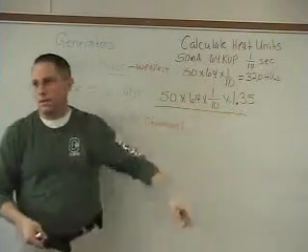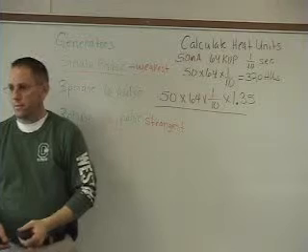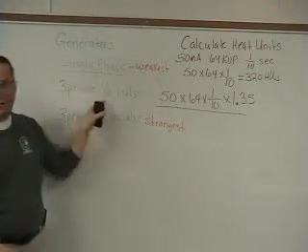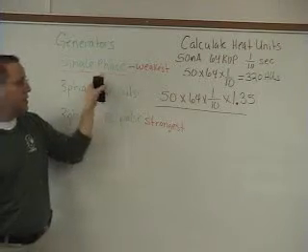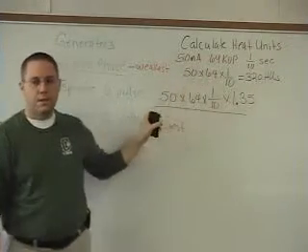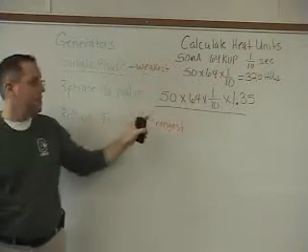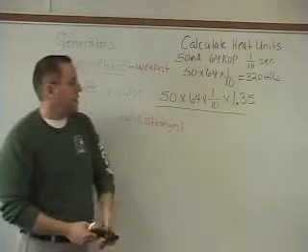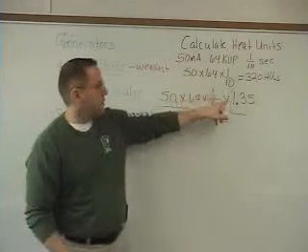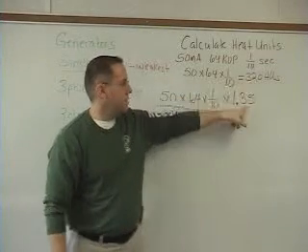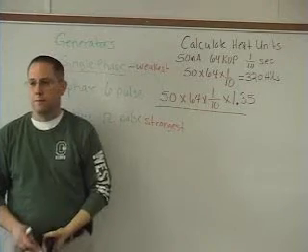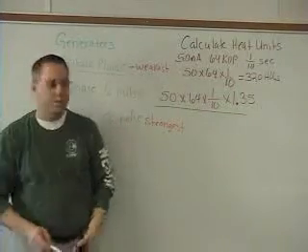That number always stays the same, 1.35. If you're doing a single phase, it's just the 3 numbers. If it's 3-phase 6-pulse, then you also multiply by 1.35. We know the first 3 are 320, so take that times 1.35, which equals 432.